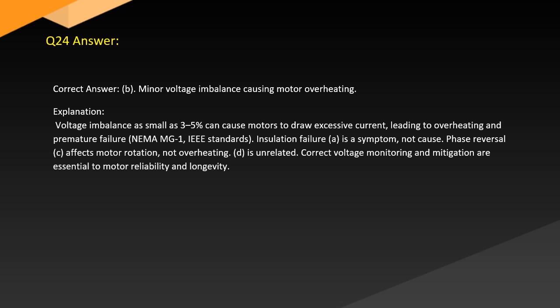Answer. Correct answer: B. Minor voltage imbalance causing motor overheating. Explanation. Voltage imbalance as small as 3–5% can cause motors to draw excessive current, leading to overheating and premature failure. See NEMA MG1 standards. Insulation failure, A, is a symptom, not a cause. Phase reversal, C, affects motor rotation, not overheating. D is unrelated. Correct voltage monitoring and mitigation are essential to motor reliability and longevity.